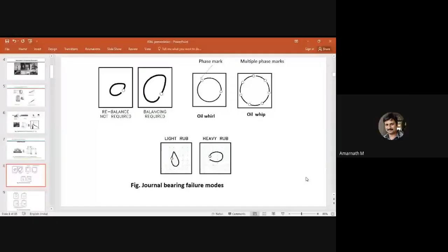So in a turbine, if the shaft needs balancing, it will give you the details of operating condition. This is called as orbit analysis. These are the results obtained from journal bearing operating condition through displacement probes mounted on the journal bearing housing in this fashion. So the displacement probe will give the details of balancing. Then oil whirl, oil whip. You can see the phase mark for oil whirl in that fashion, 2 phase marks. In oil whip there are multiple phase marks. If there is a light rub, you will get this kind of signature, and for heavy rub. So these are some operating conditions found by using displacement probe in journal bearing system.